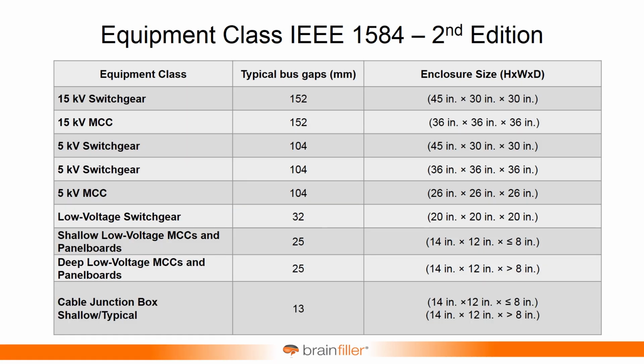And the bus gaps, the gap between the bus bars, they're just kind of typical. Most people leave these because you don't know what else to use. And within any piece of equipment, you can have different spacings at different locations in the equipment. And then these are the enclosures that were used for the original 2002 standard. Well, as I said, with almost 1,900, approaching 2,000 new tests, this was greatly expanded.